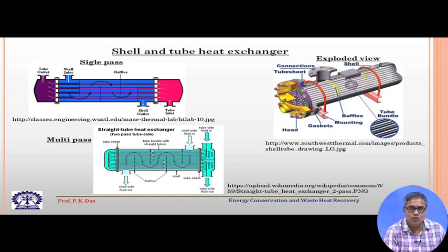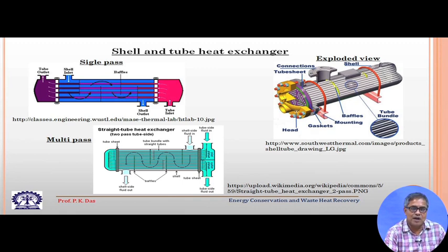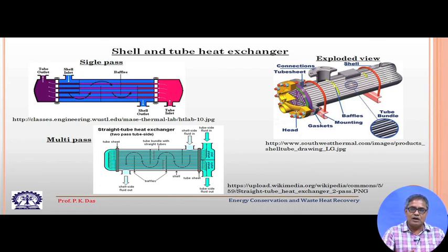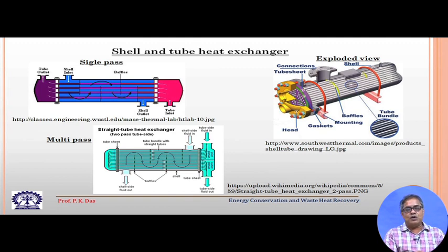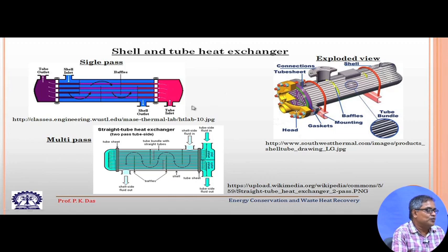The problem with a tube-in-tube heat exchanger is that it will have a very large length for a given heat duty unless we do some design modification. What is most commonly done is to use a shell and tube heat exchanger. In a shell and tube heat exchanger the construction is also mainly tubular, but instead of one central tube we have a number of tubes through which one fluid passes, and these tubes are arranged inside a shell — essentially another tube with a large diameter.